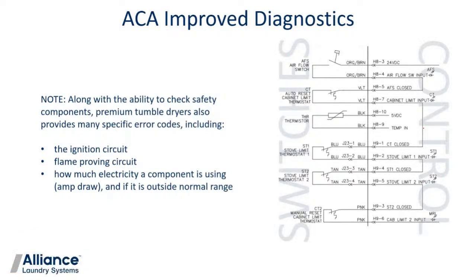We find the error codes in the programming manual. Dustin, I think, has a nice section towards the end here where we can help you find the correct programming manual. Absolutely, which will help you with these error codes. But the point here is, before, if we had a no heat condition, which means we have component failure, we really had to have it together, or we'd have to call a technician. Now this current system is going to produce an error code that might say something like, hey, you have a stove limit thermostat number 1 is open. And we can go look at that. And like I said in a previous slide, if we have one of those open, that means I've got an airflow problem. So it's going to point us in the correct direction with some simple interpretation.